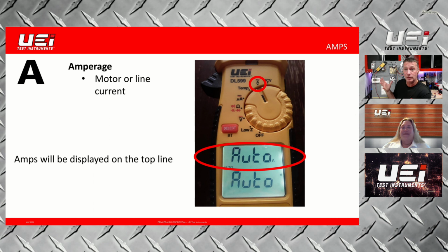With this particular one, if we apply a small load to it, let's say we energize our fan relay and bring on our fan, we're now actually going to be reading some current drawn across that, simply from the magnetic induction going through our conductor.